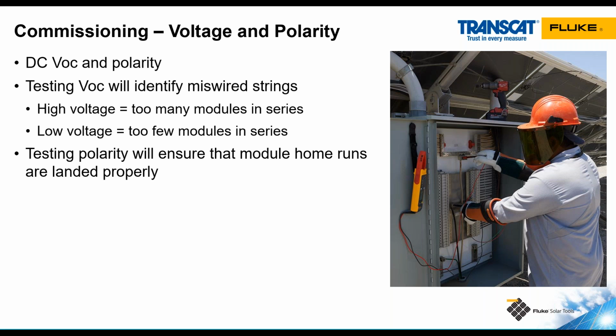It's a safety hazard to the technician, and it may cause that fuse holder to melt, which will melt the fuse holders adjacent to it. It may cause a cascading catastrophic failure. Very important to test voltage and polarity at commissioning before the fuse holders are closed and the system is turned on.